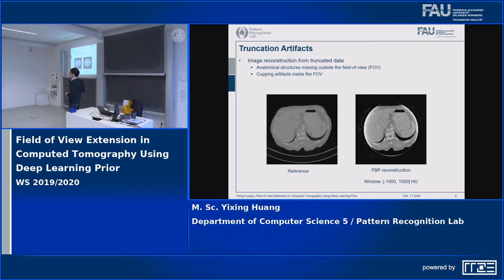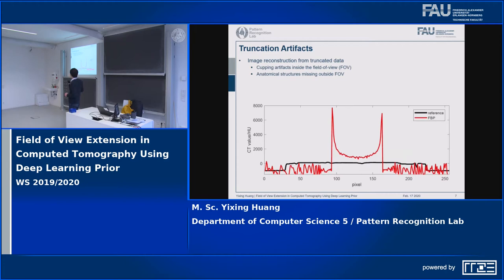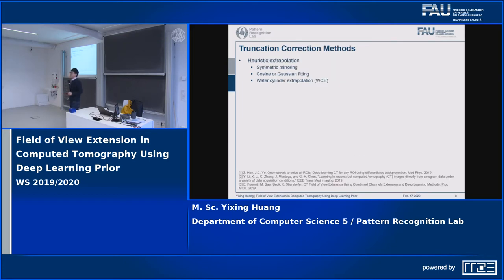Image reconstruction from truncated data using classic FBP reconstruction will suffer from artifacts. Here is the reference image, and here is the FBP reconstruction — we can clearly observe the FOV boundary. The anatomical structures outside the FOV are missing, and the intensity values inside the FOV are much larger and brighter than the reference. We call these cupping artifacts, because if we plot a line profile, the intensities look like a cup.